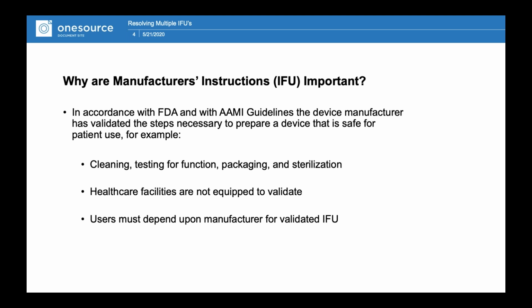You'll notice in the market, if you go look at your IFUs, you're starting to see very, very detailed instructions on cleaning, whether the device requires sonication, to be put in a sonic, whether the device needs to be taken apart, because some devices need to come apart for cleaning. And then I'm starting to see, and you will start to see, actually instructions for your washers, for the mechanical washers that we use. We're starting to see cycle settings show up.